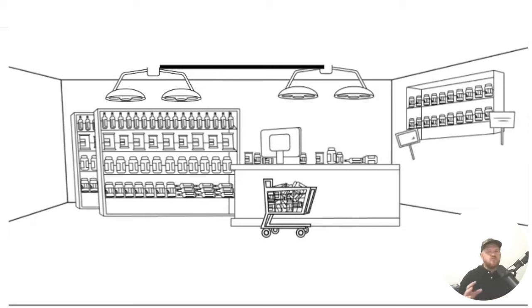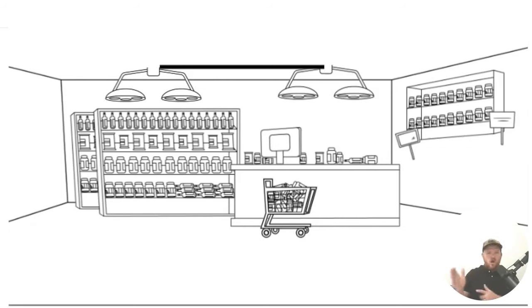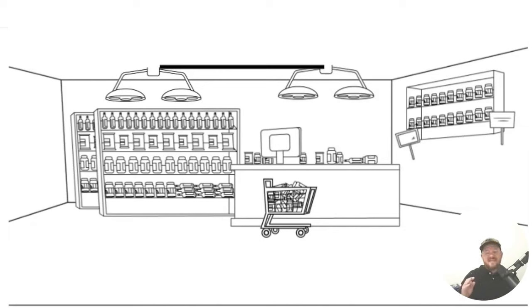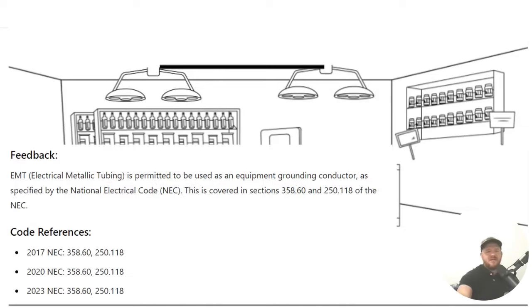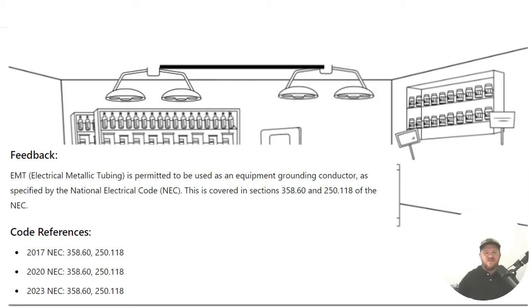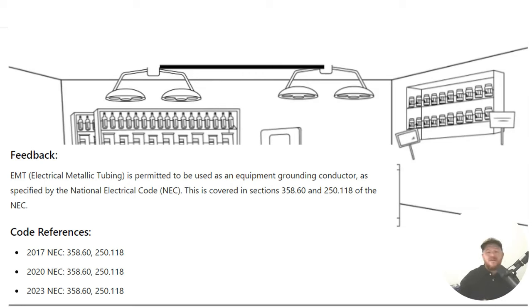And we're going to have to go to a couple different code sections for this. And just to make sure that I'm being clear, just so you understand, from this light on the left-hand side over to the new light on the other side. As you go from this side to that side, you could potentially just run a hot and a neutral over there and use that equipment, or excuse me, use the EMT itself as an equipment grounding conductor. Let's go ahead and take a look at it here. EMT, electrical metallic tubing, is permitted to be used as an equipment grounding conductor as specified in 358.60 and in 250.118.